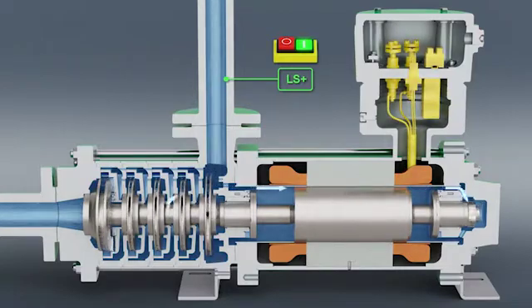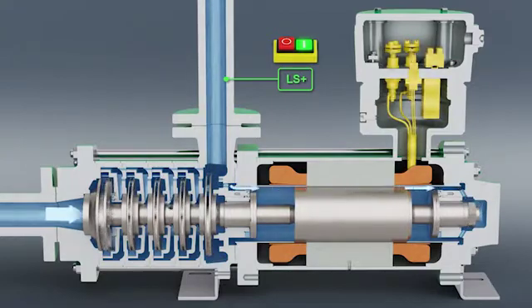This partial flow passes over the rotor and returns through the hollow bore shaft and exits back between the impellers in the low pressure area of the pump. The hermetic multistage canned motor pump works with hydrodynamic bearings and is in continuous operation wear and maintenance free.